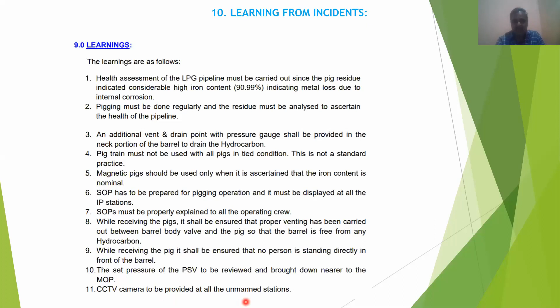While receiving the pigs, it shall be ensured that proper venting has been carried out between the barrel body valve and the pig so that the barrel is free from any hydrocarbon. It was not done there. While receiving the pig, it shall be ensured that no person is standing directly in front of the barrel. The set pressure of PSV to be reviewed and brought down near to the MOP. CCTV cameras to be provided at all the unmanned stations.